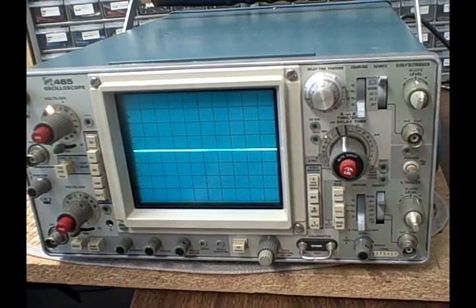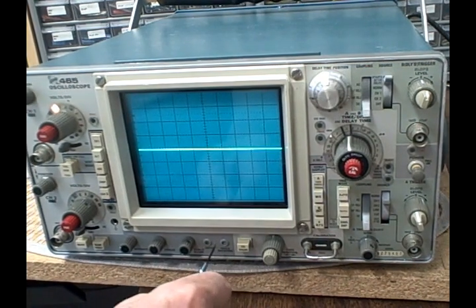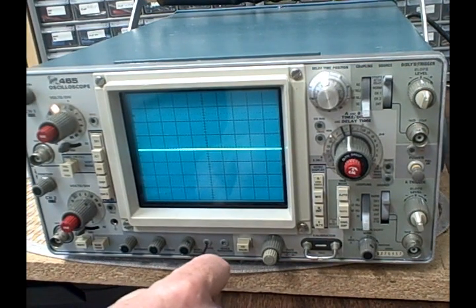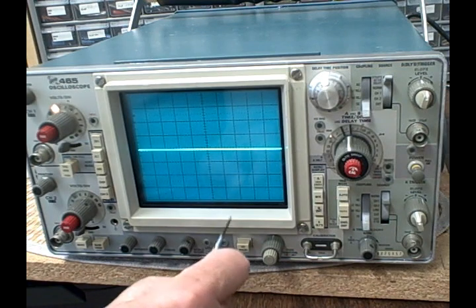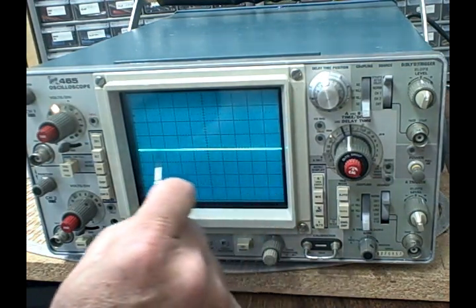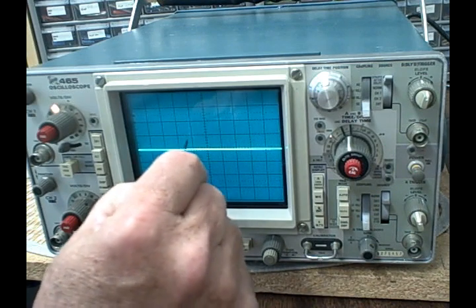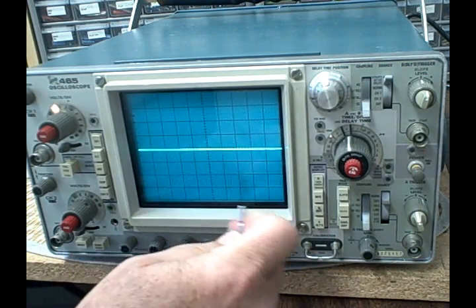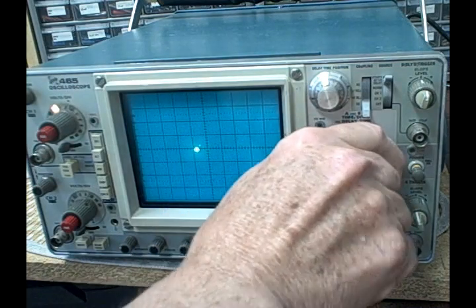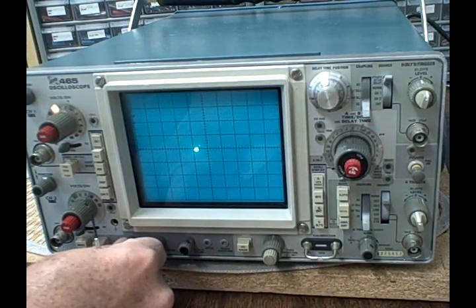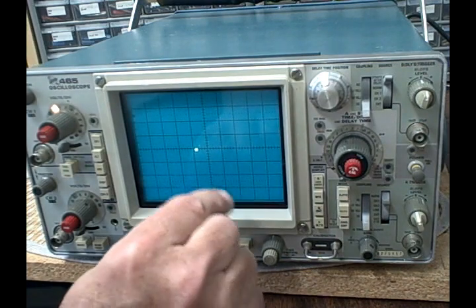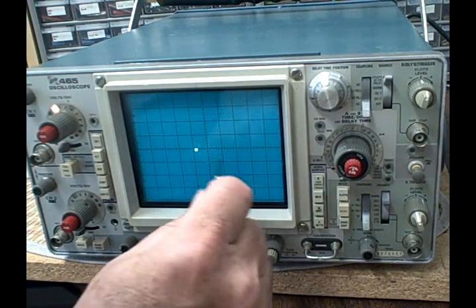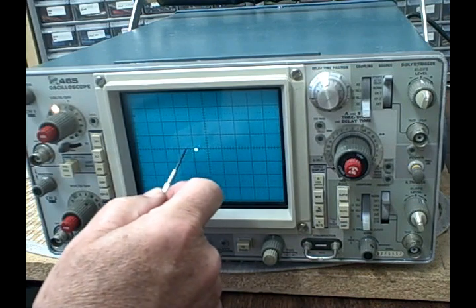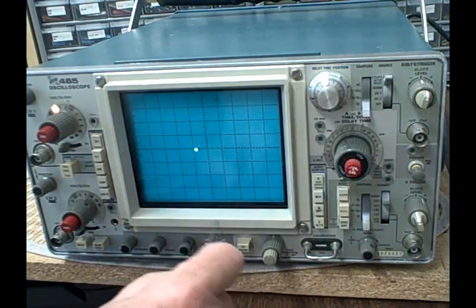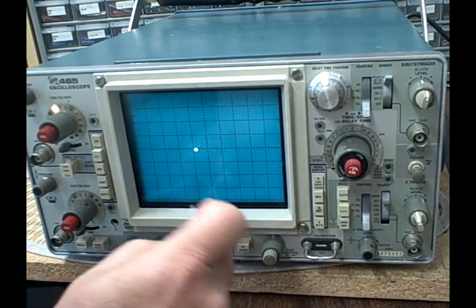So here's a couple of other things I just want to point out. There's no knob on it. It's done with a screwdriver, but there's an adjustment here for astigmatism. And what that does is it sharpens the trace by, say when you put a point on here, instead of, well, let's show you. There's a point. And what you do with that astigmatism is you adjust that point for the best roundness. Otherwise, it could look like a small line or a dash. That's not adjusted right. When you've got it round, that's right. That's going to give you the best trace.